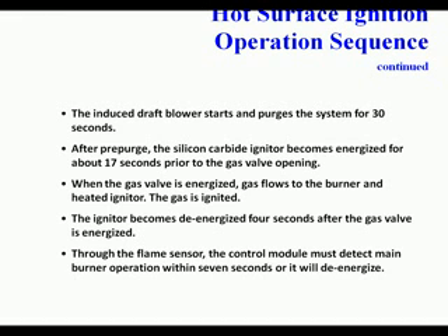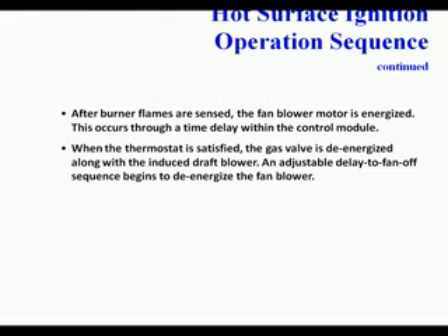The induced draft motor starts and purges the system for 30 seconds. After pre-purge, the igniter becomes energized for about 17 seconds prior to the gas valve opening. When the gas valve is energized, the gas flows to the burner and the heated igniter. This gas is ignited. The igniter becomes de-energized 4 seconds after the gas valve is energized, and through the flame sensor, the control module must detect the main burner operation within 7 seconds or it will de-energize.